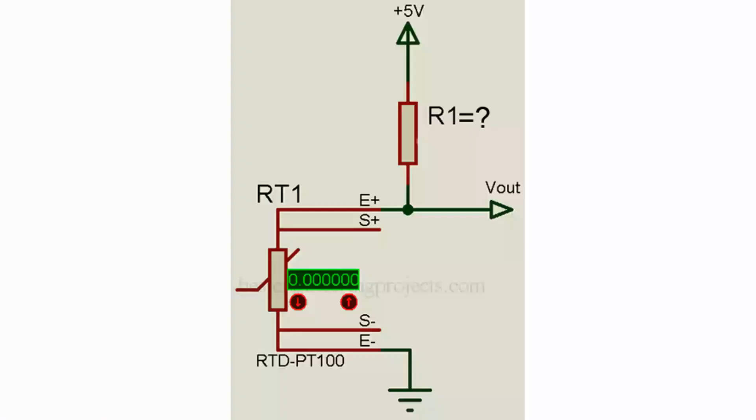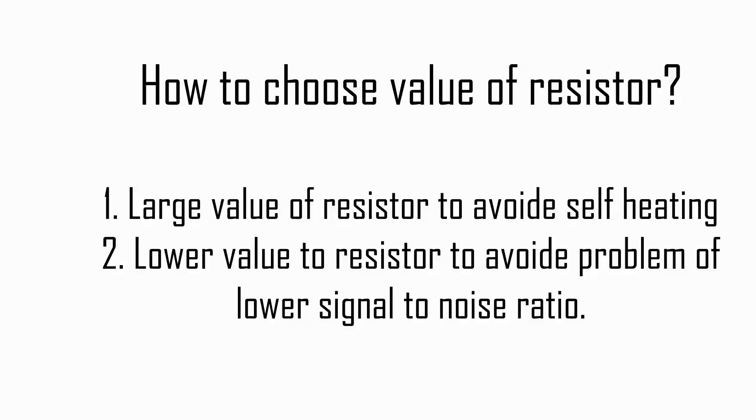Now a simple voltage divider network is designed using constant voltage source, a constant resistor and PT100. While choosing the value of this constant resistance R1, we have to consider few things. One, value of resistor R must be great enough in order to avoid the self-heating problem. If we use low value resistance, more voltage drops across PT100. As a result, more self-heating. This increases error.